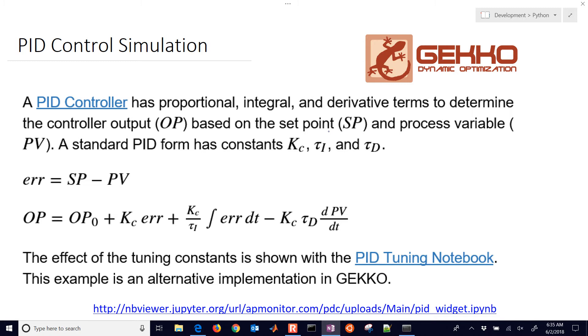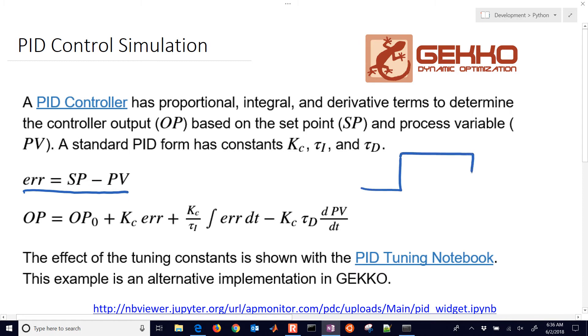The very first thing we need is to calculate the error, which is the difference between the set point and the PV. The set point is trying to be reached by the PV, and the difference between those two at any point is going to be the error. Mathematically, it's simply the set point minus the PV.